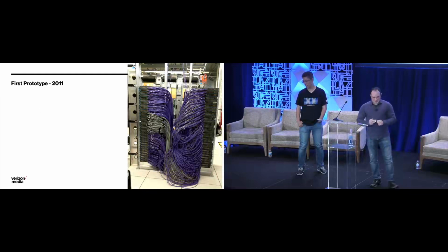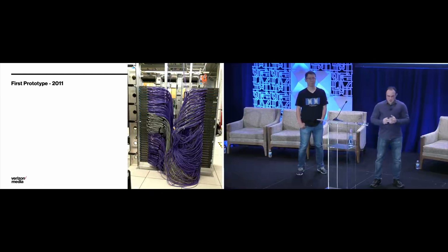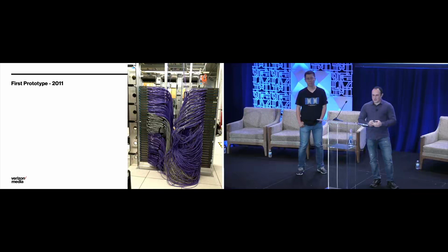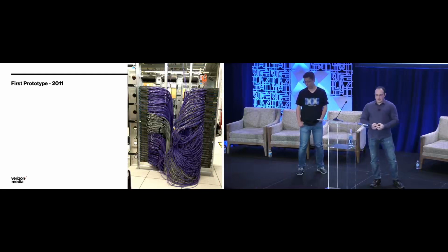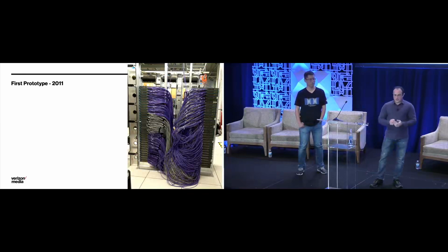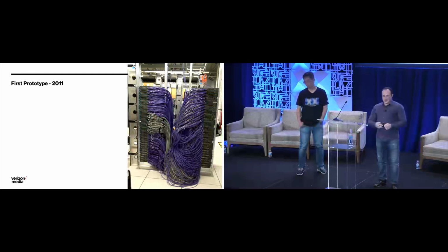and the mock-up served two purposes. One is we needed to see what a miswire rate is going to be in a typical data center. So our two most careful guys, 2,000 ports, how many are going to be messed up? The answer was roughly 5%. So clearly we needed something to make it harder to make mistakes, to make it easier to do things correctly. Also, this spoke quite loudly of the need for automation to be written in order to verify the wiring.